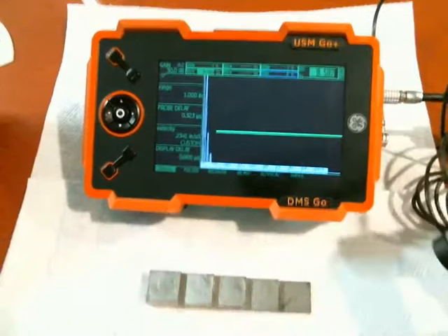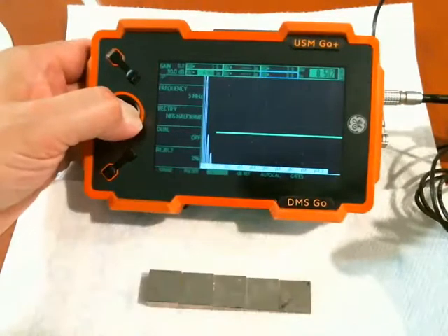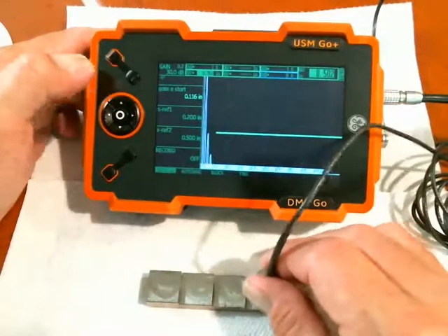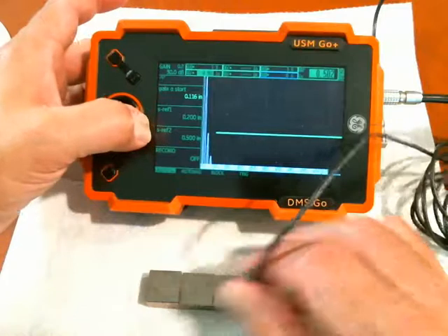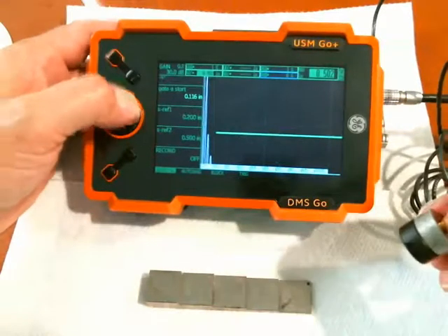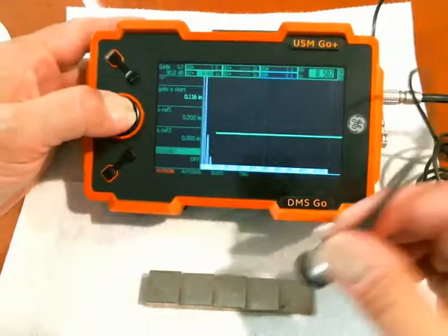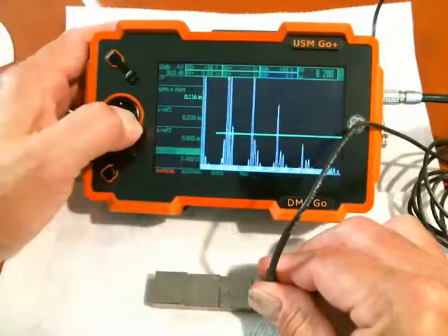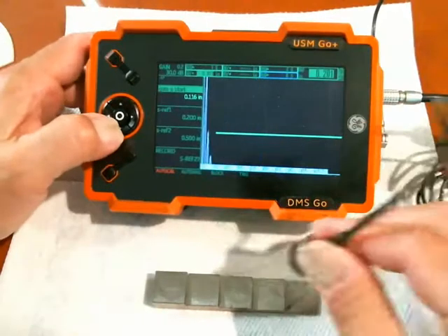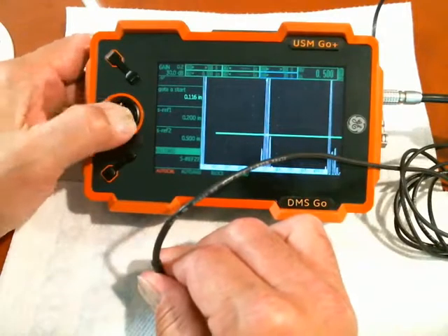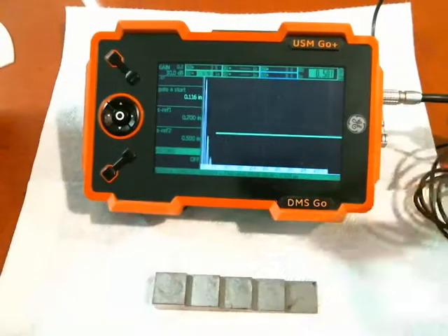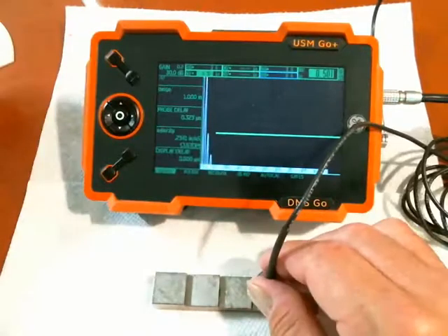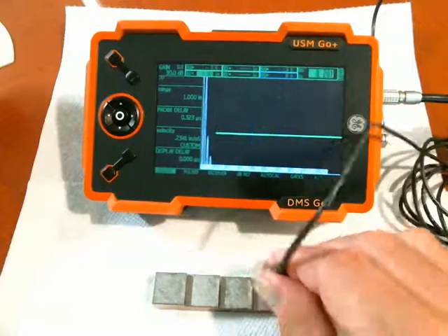To recap: we go to the auto cal menu and go up one click. We have sref1 and sref2 — the thin block and the thick block — programmed in. Go to record, click right once for sref1 on the thin block, then again for sref2 on the thick block. It automatically calculates the velocity and the probe delay required to take our reading. That is how auto calibration works.